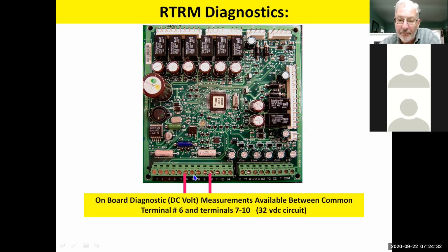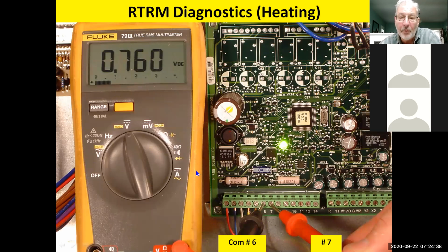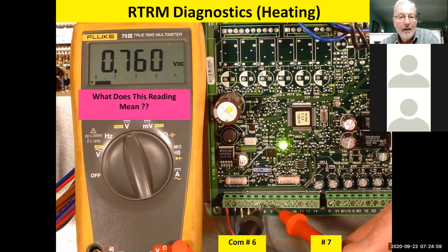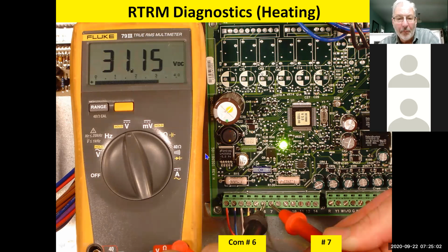So this is a 32-volt circuit, and if it's in a lockout, you're going to find some information here that's valuable when you're working on the board. So if I go to my heating diagnostic, which is terminal 6 and 7, and I see less than 1 volt DC, that means I don't have an active call for heating at that point. Okay, there should be nothing running if we're at less than 1 volt DC. If I go to this terminal and I see probably 28 to 32 volts, somewhere in that area, that's telling me I have an active call for heating at that point, and there should be something running. The system should be on at that point.